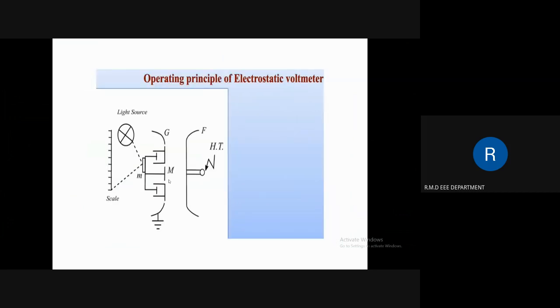I'll explain the operating principle again. The setup consists of the G terminal and the F terminal, the parallel plates, and M is the moving plate. G represents the guard rings, M represents the moving disc, and F represents the fixed plate. When high voltage is provided to this fixed plate, a scale with a light source is connected to the moving plate.